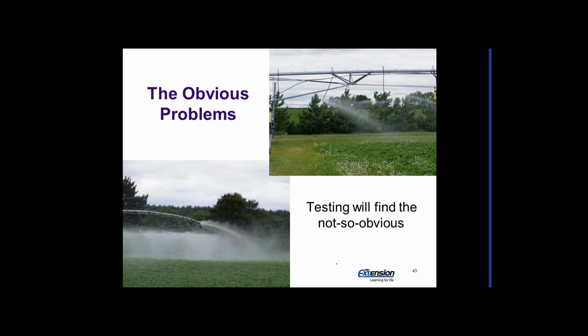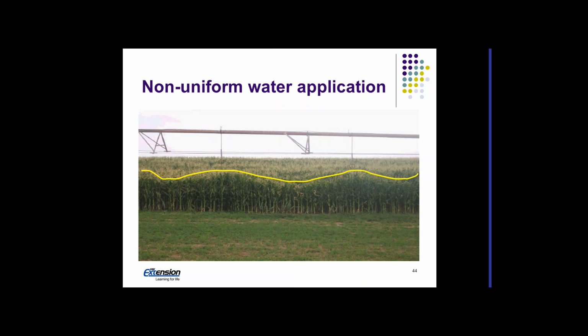So this test doesn't catch the obvious problems. Those we can usually see. So here's one where we've got a boot at the end or a drain valve that's not sealing properly, and here's a nozzle that may not be spinning. It may be stuck in one spot, or part of it's not working. These are supposed to have multiple streams out, and this may only have one, so it's not working properly. Those problems we can typically see if we take time to look at the system.